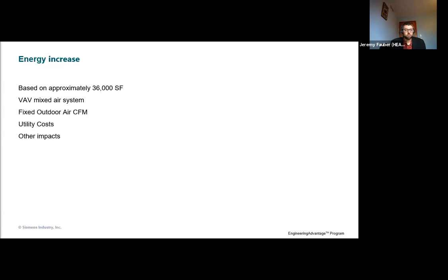I looked at this in terms of having a fixed outdoor air CFM. What that means is even as your recirculation air increases or decreases, the outside air quantity always stays the same. That's the way ASHRAE 62 wants you to do it. And the reality is, in order to do that with a VAV system, you likely need airflow measurement to be holding that set point.